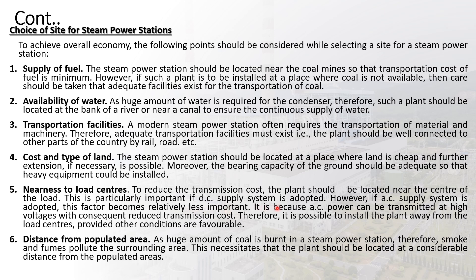If a DC supply system is adopted, the plant must be near the load center. However, if an AC supply system is adopted, this factor becomes relatively less important. It is because AC power can be transmitted at high voltages with consequent reduced transmission cost. Therefore, it is possible to install the plant away from load centers, provided other conditions are favourable.